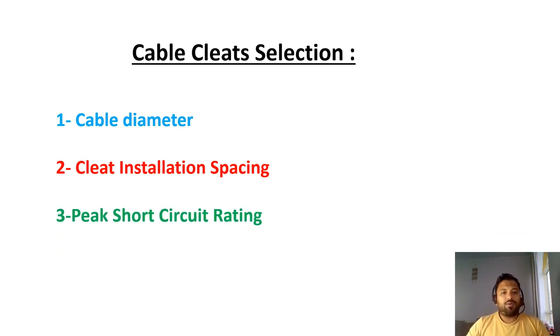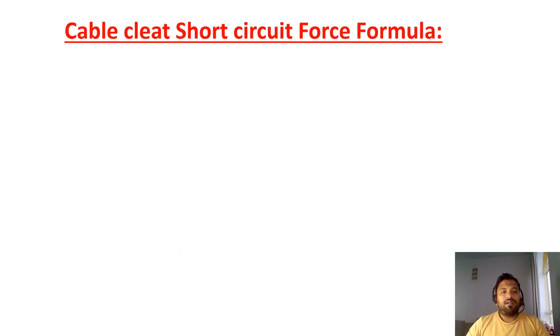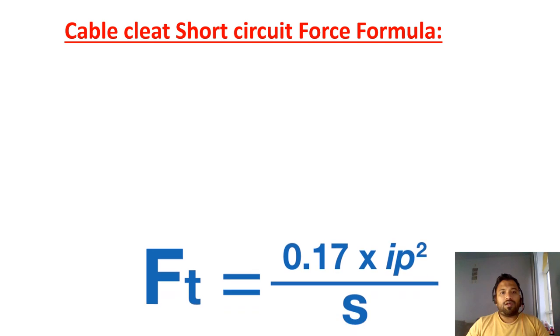Third thing is peak short circuit current rating. This can be get from the calculation. So it looks like this one. So you are on a cable ladder. You are installing a cable. Between cables, these you see these points are the cleats. Between the cleat distance, this D is the distance between the two cleats. Now we will see the cable short circuit formula. How it looks like.